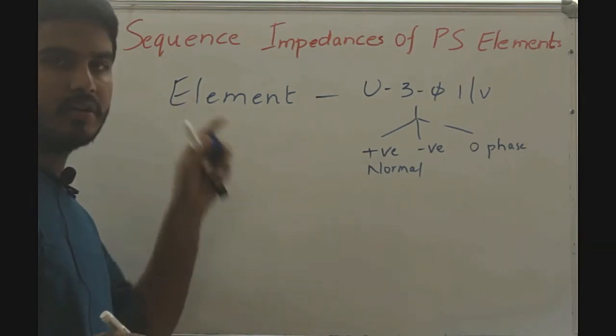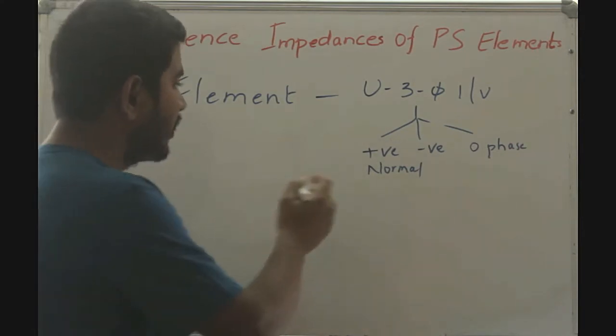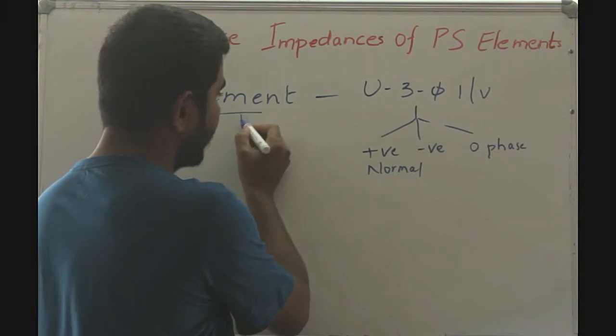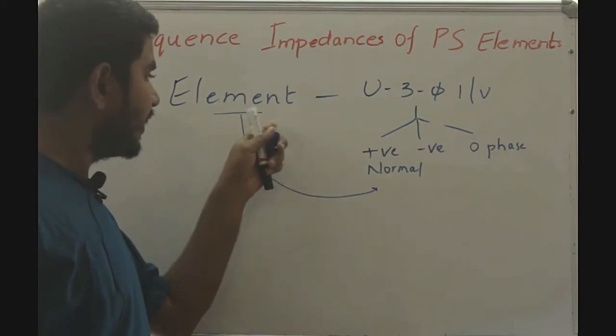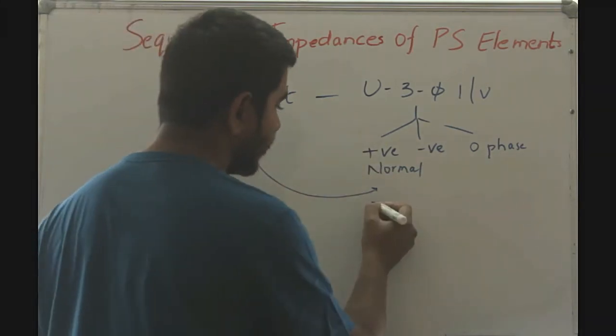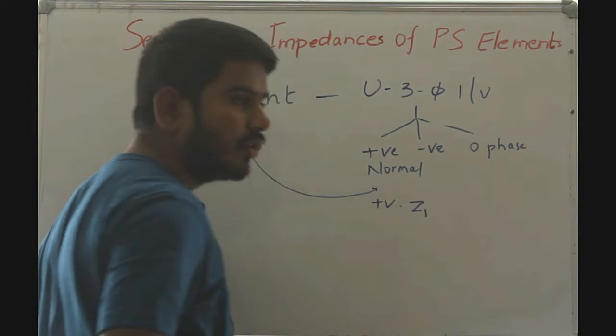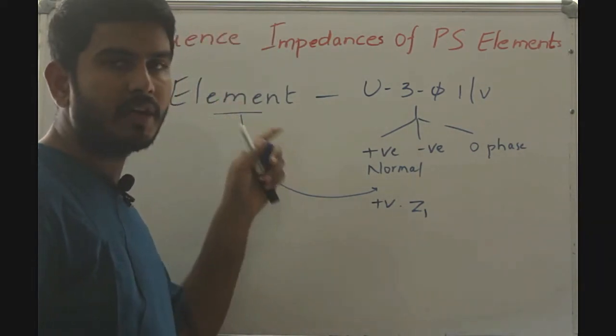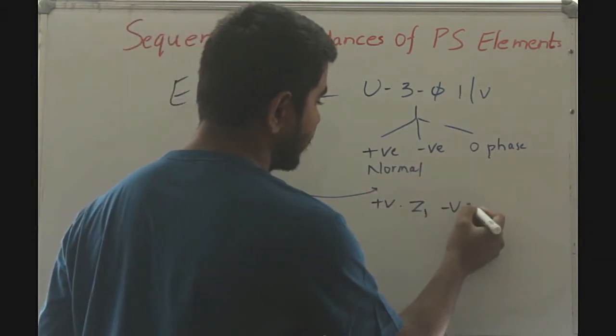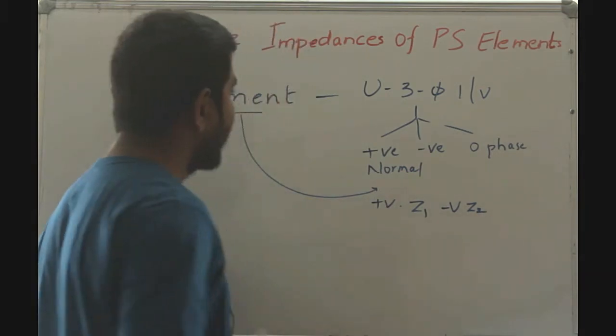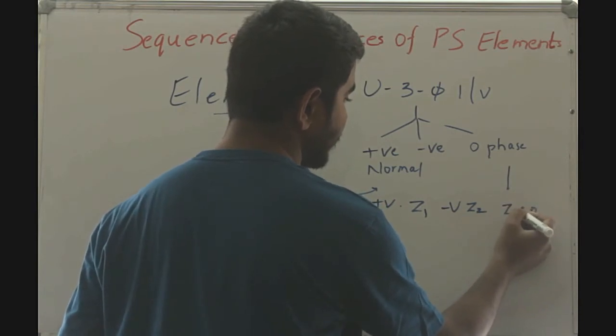Each element or circuit in the power system will offer a different impedance to a different sequence current. The impedance offered by the element to the positive sequence current is called the positive sequence impedance, with subscript 1. The impedance to the negative sequence current is the negative sequence impedance, with subscript 2. The impedance to the zero phase sequence current is the zero phase sequence impedance.